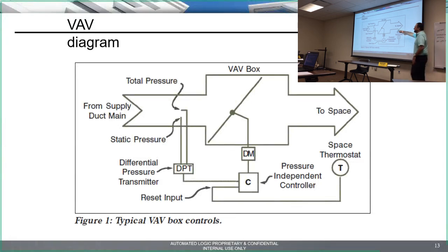So in the end of the box, you see we've got a differential pressure transmitter, and that's what this DPT stands for. The differential pressure transmitter is measuring the difference between total static and external static. If you can imagine the air's flowing down through this duct, right? It's flowing down through here, and the pressure hits the end of this tube. Well, that pressure hitting the end of the tube is more than the static pressure. Static pressure is like when I blow up a balloon. The more you blow on the balloon, the bigger it gets. The more pressure I'm putting externally on the actual walls of the balloon itself. And that's what this static pressure is.